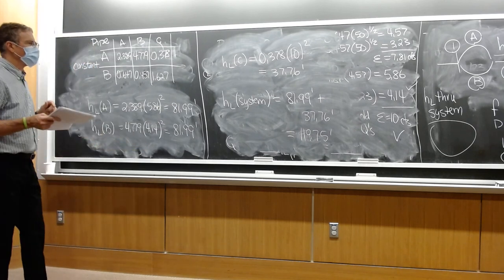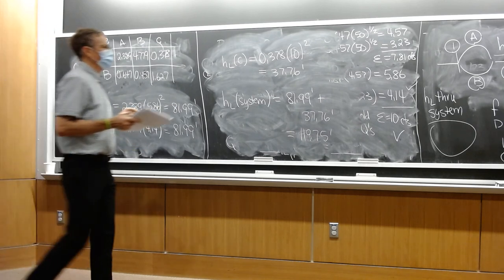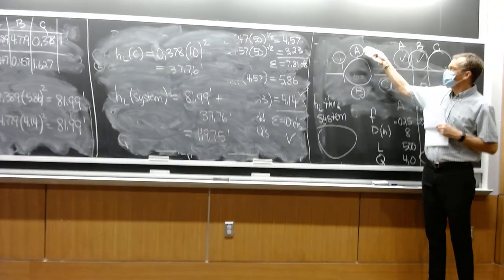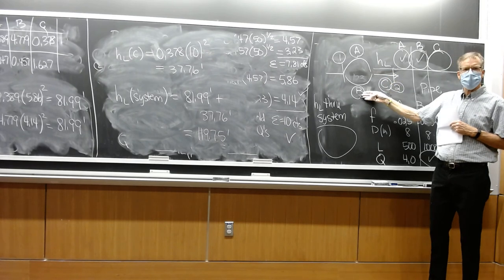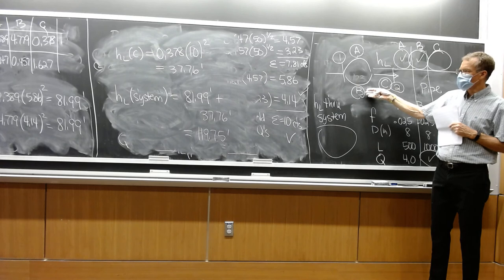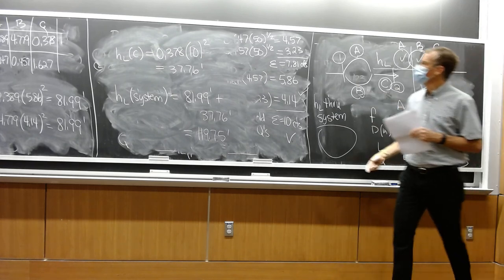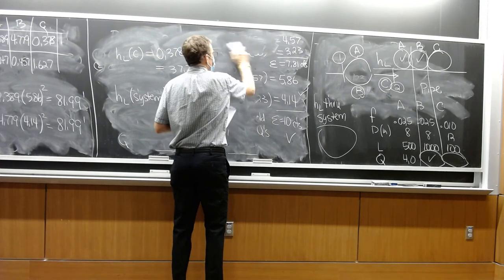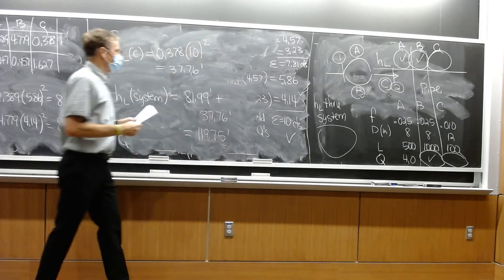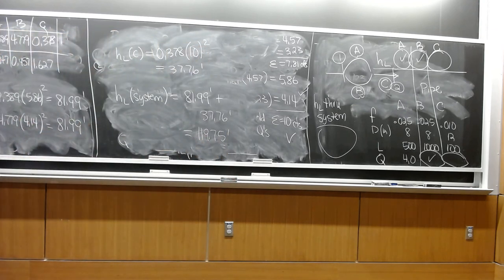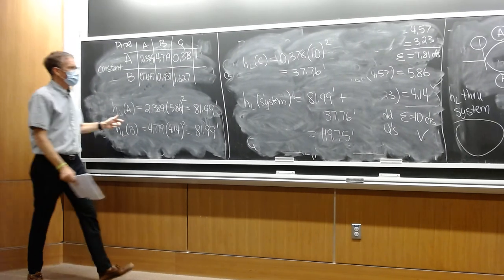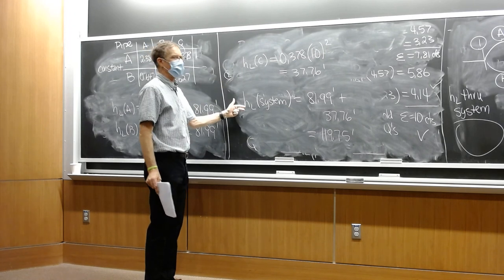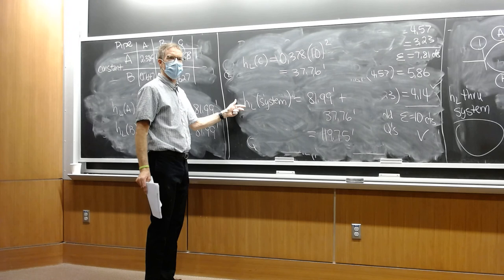So just to review, we had a case where we have a total, but we don't know the distribution between the branches. We guessed a head loss. We calculated flows for the branches. Then we scaled up the flows to get the correct total, recalculated the head losses, calculated the head loss through the third pipe in the system, and then calculated the system head loss.